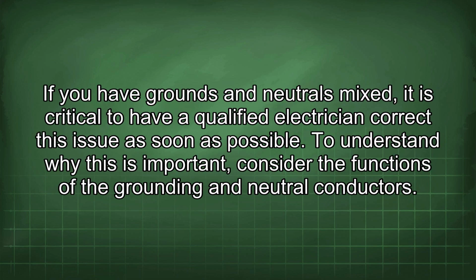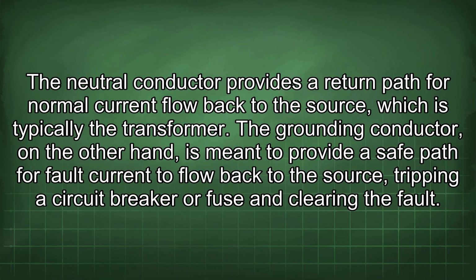If you have grounds and neutrals mixed, it is critical to have a qualified electrician correct this issue as soon as possible. To understand why this is important, consider the functions of the grounding and neutral conductors. The neutral conductor provides a return path for normal current flow back to the source, which is typically the transformer. The grounding conductor, on the other hand, is meant to provide a safe path for fault current to flow back to the source, tripping a circuit breaker or fuse and clearing the fault.